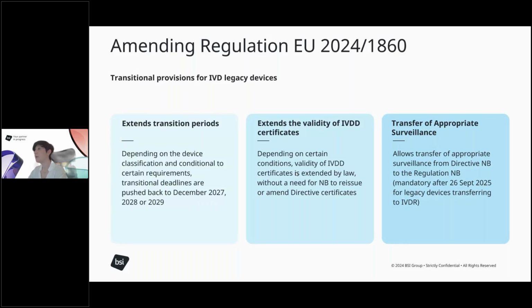It also introduced the concept of transfer of appropriate surveillance for IVDD, similarly to what happened in the 607. So it allows the transfer of appropriate surveillance for legacy devices from the directive notified body that issued the certificate to the regulation notified body, if those notified bodies are different. And this must be completed and requested by the 26th of September 2025.